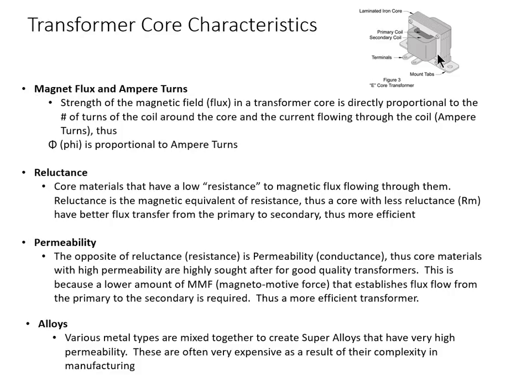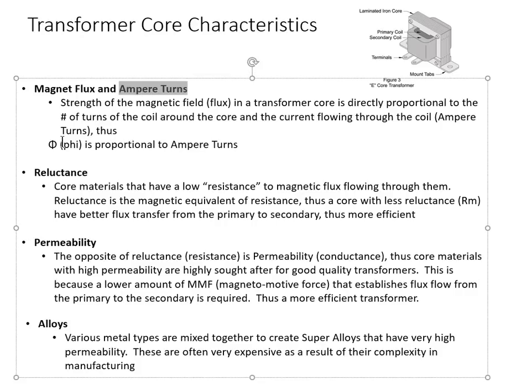First off, there's something called magnetic flux, the magnetic currents that flow inside of this core. The strength of the magnetic flux in a transformer is directly proportional to two things: the number of turns of coil around the core in the primary, and the current flowing through the coil, something known as ampere turns. So magnetic flux is proportional to ampere turns. The higher the current you feed this thing with and the more wraps it has around the primary, the more magnetic flux you will have flow.